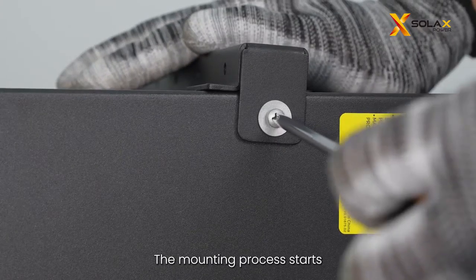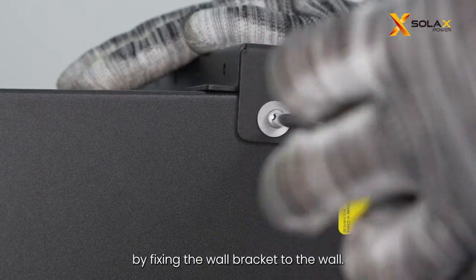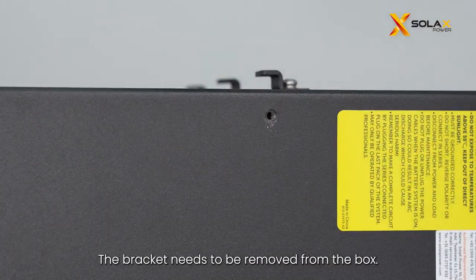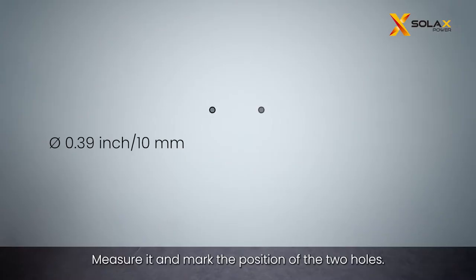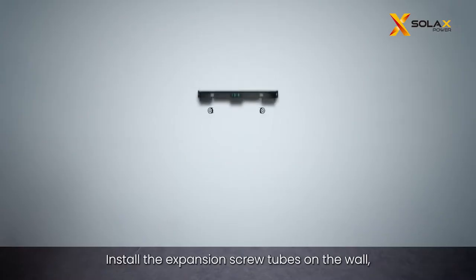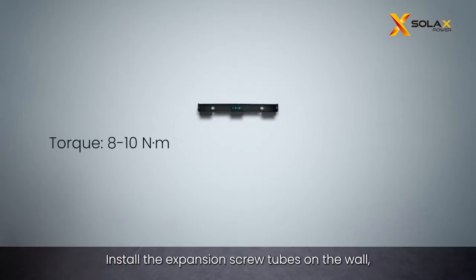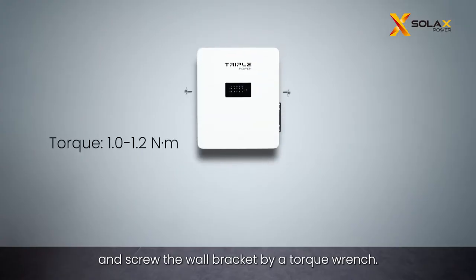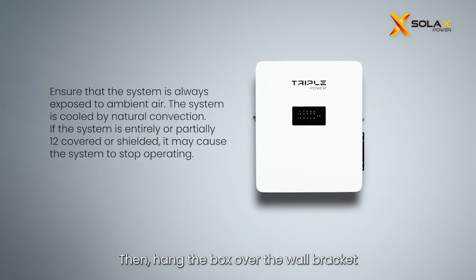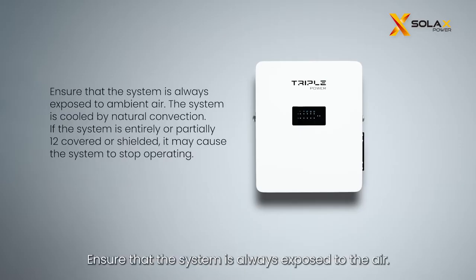The mounting process starts by fixing the wall bracket to the wall. The bracket needs to be removed from the box. Measure it and mark the position of the two holes. Install the expansion screw tubes on the wall and screw the wall bracket by a torque wrench. Then, hang the box over the wall bracket and align it with precision. Ensure that the system is always exposed to the air.